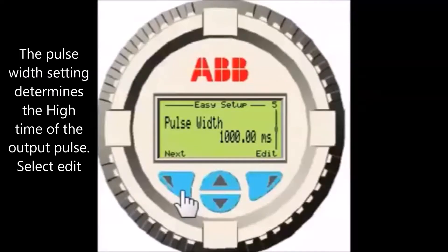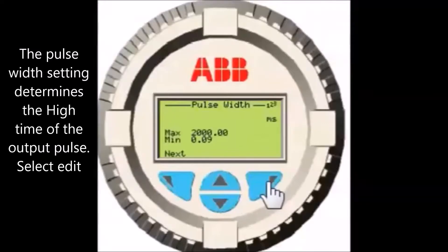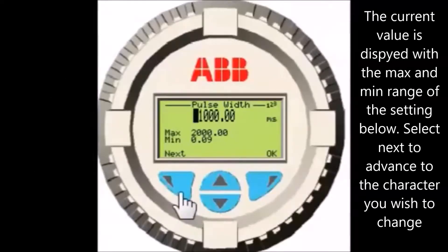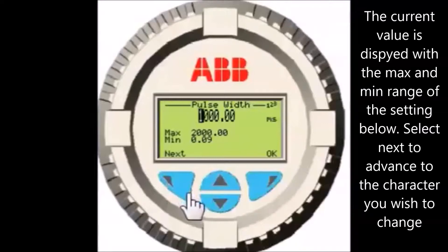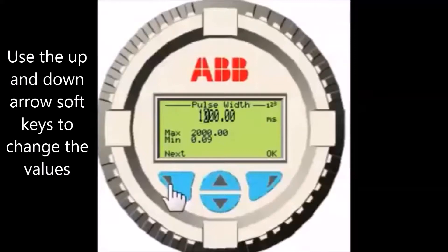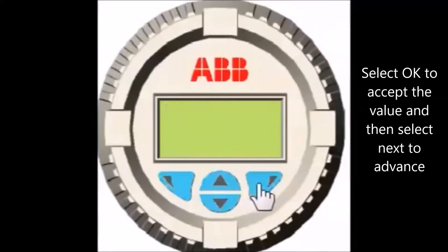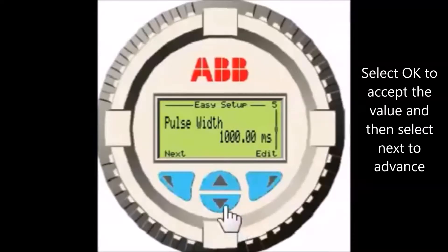Pulse width sets the high time of your output pulse. The device you are sending the pulse to will determine the minimum width of the pulse you must output — relays require a longer pulse than digital inputs. The current setting is displayed and the maximum and minimum values are shown below; these settings cannot be exceeded. Select Edit, then Next to place the cursor over the first character. Use the up and down arrow keys to change the character, select Next to advance to the next character, select OK to accept the value, and then Next to advance.